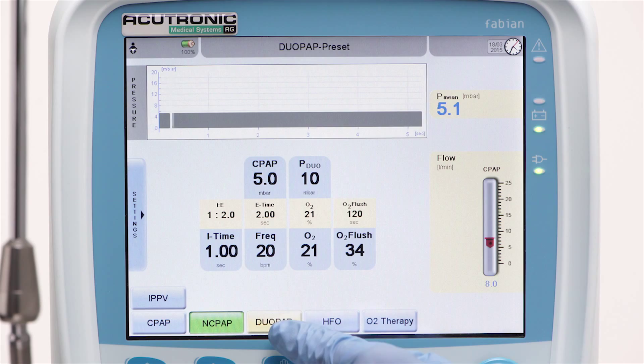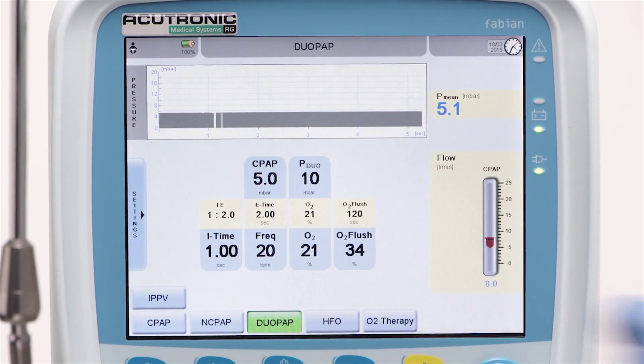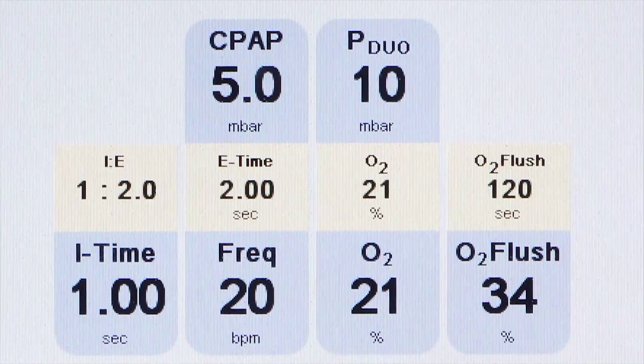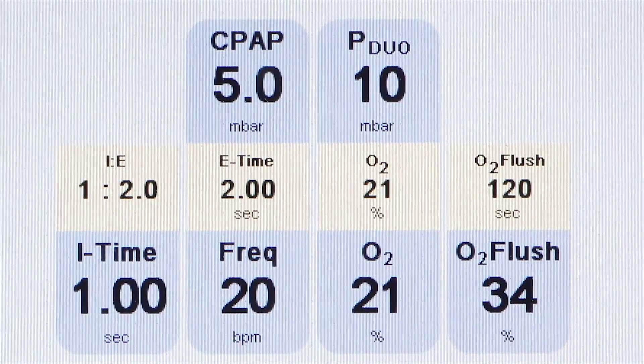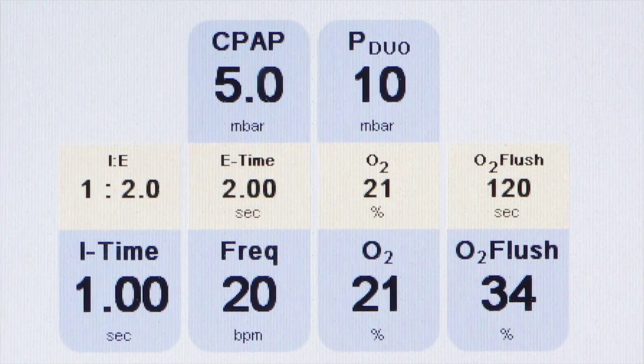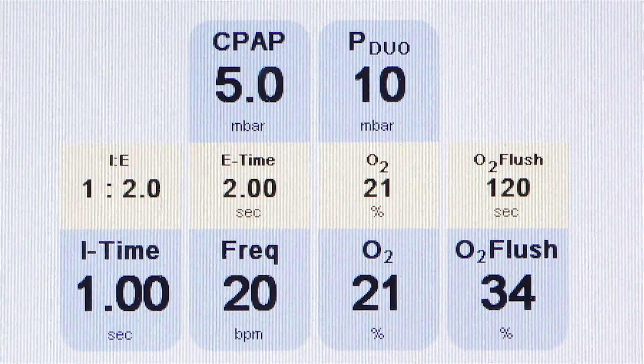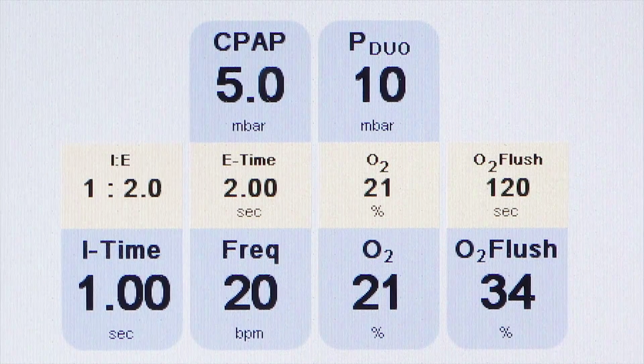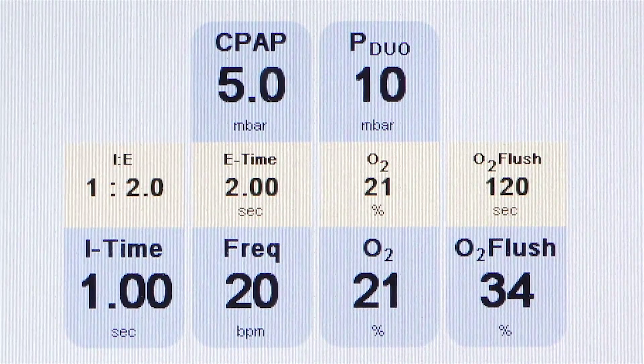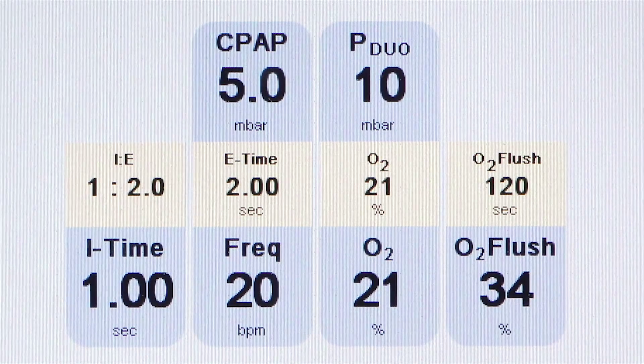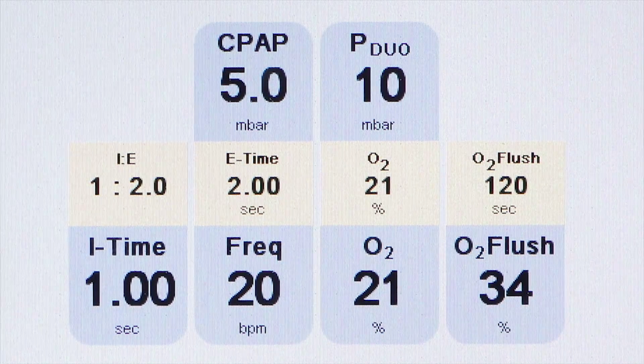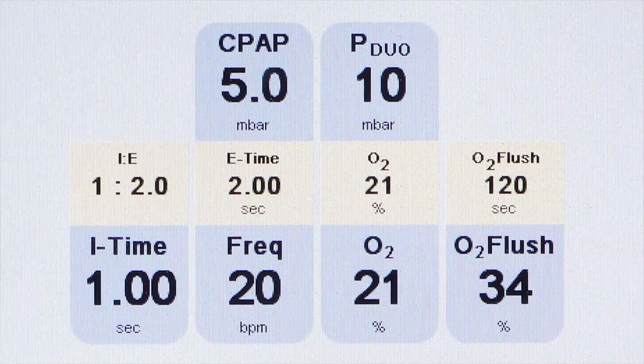In DUO-PAP, the following parameters need to be set: the CPAP level, the P-DUO upper pressure level, the inspiratory time, the frequency of the bilevel transitions per minute, and the O2 and O2 flush as needed.